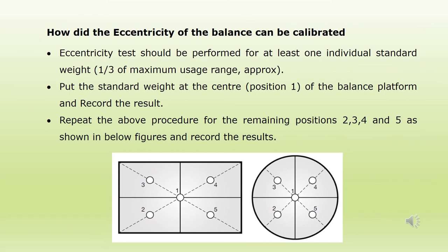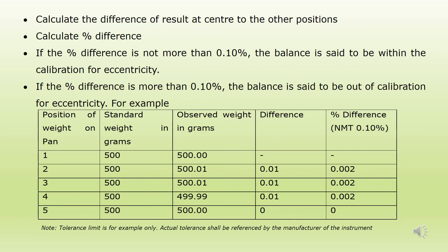How can the eccentricity of a balance be calibrated? Eccentricity tests should be performed for at least one individual standard weight, placing the weight in different possible positions: left top, right top, left bottom, and right bottom, as shown in the diagram. The difference and percentage difference in observed weights from center to the other positions is calculated. If the percentage difference is within the tolerance limit, the balance is said to be within calibration for eccentricity.